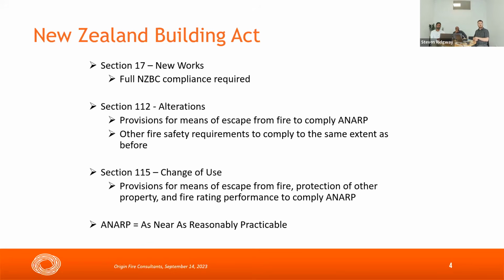ANARP is a word that you'll hear quite a bit if you deal with fire engineers. So as I said, as near as reasonably practicable. If it's an easy fix, you're going to do it. If it's not easy, it comes down to the life safety benefit in comparison with the cost in relation to the project. So if you have a small fit out, a big upgrade is not reasonable, but if you're gutting the building back to the superstructure, a big upgrade is expected.